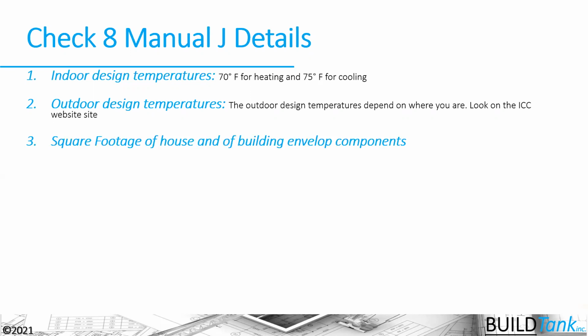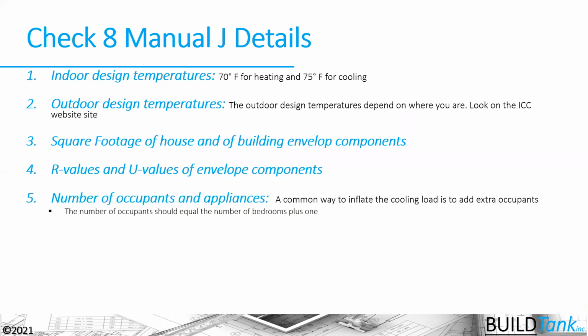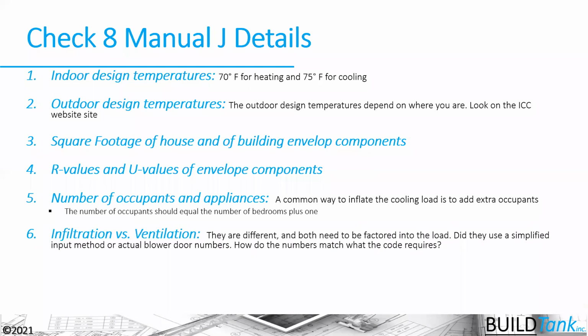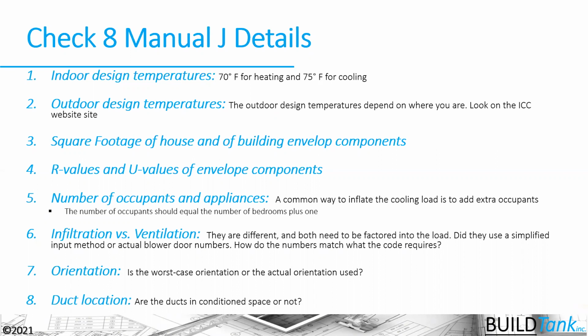We need to look at how they did their takeoffs for the square footage of the building thermal envelope and the different components there. We need to look at the R-values and U-values that they're using and the assumptions that they're using. Are they based off of the specifications of the house or not? The number of occupants that they're putting in and the appliances they're putting into that house, that infiltration and ventilation load, again, are they accounted for separately or not? The orientation of the house and the duct location, and ultimately leakage of that house there.